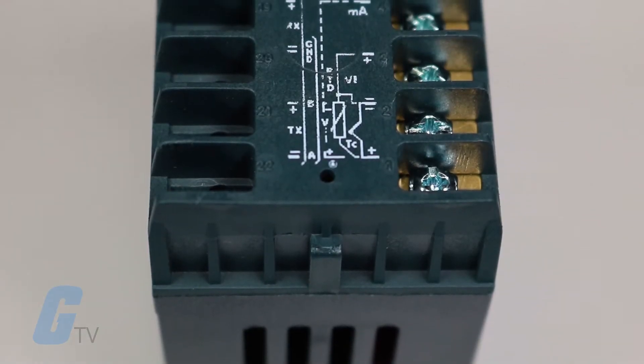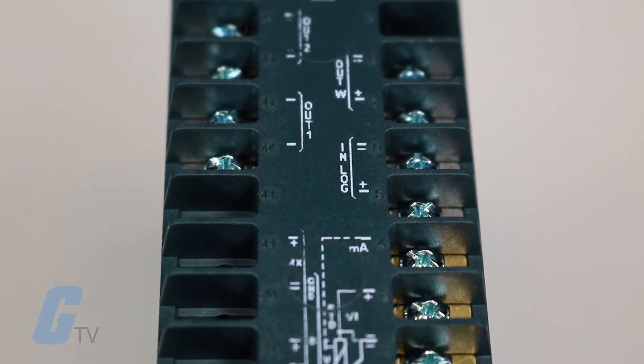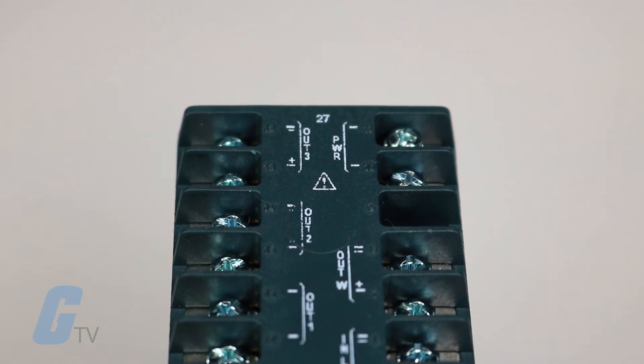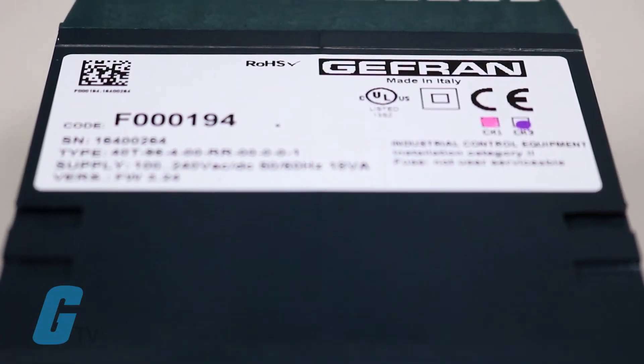The instruments have a maximum of 3 outputs that can be mechanical relays or logic outputs. A triac can be fitted as an alternative to the other two relay outputs, allowing you to drive resistive loads up to a maximum of 2.5 amps at 220 volts.